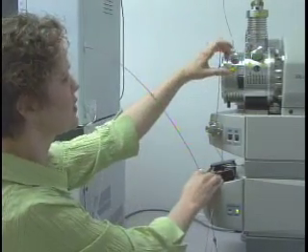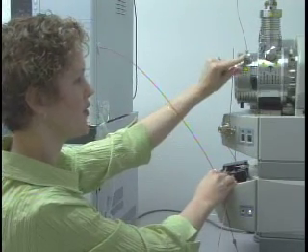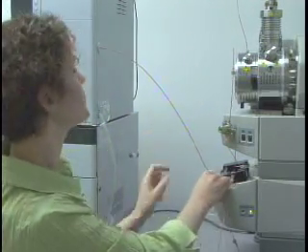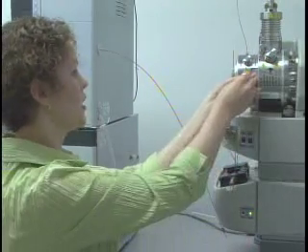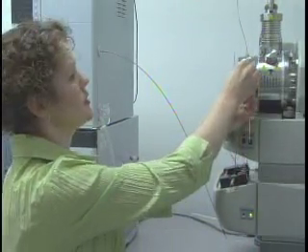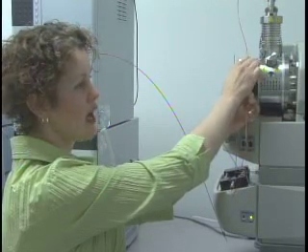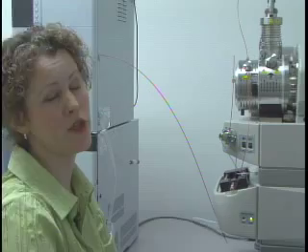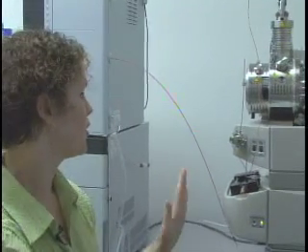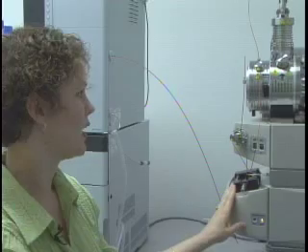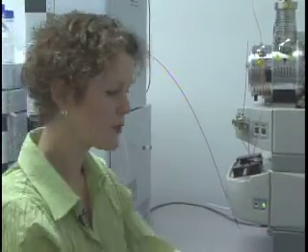If we change this little insert here, we can actually have infusion standard and mobile phase flowing into the system at the same time. The software will also perform a function called flow injection analysis, where you can have it optimize your sample and build a method for you around those parameters. But what we're going to do is the basic setup, which is infusing a compound into the instrument with the automated program.